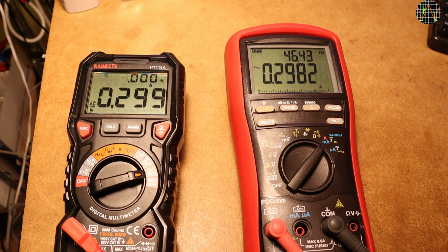In the AC amp range, the BM869S is first in displaying a frequency. It needs about 300 mA before that happens. At about 350 mA, the HT118A starts to show non-zero nonsense frequency values, and it takes at least 460 mA before the frequency approaches the correct value, at least somewhat. Even at over half an amp, it's still not stable. Compare that with the rock-solid display on the BM869S. The same happens on the milliamp range, with the HT118A needing over 3 mA compared to 1.4 mA needed by the BM869S.